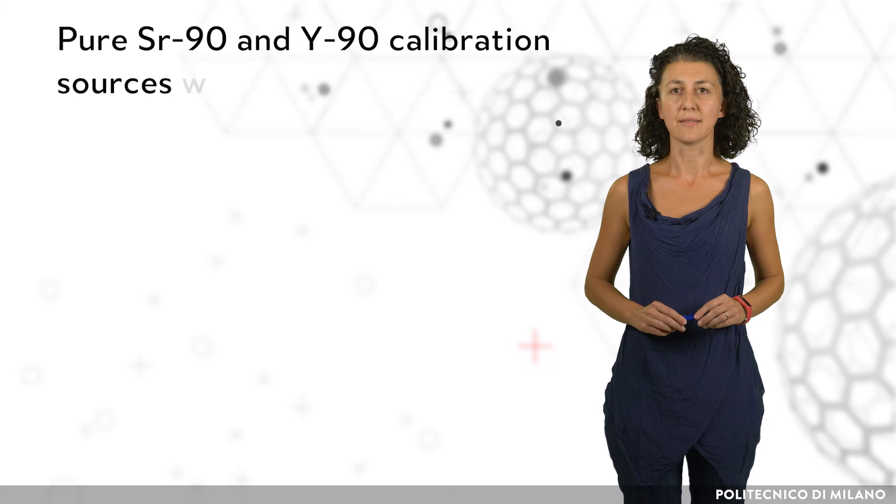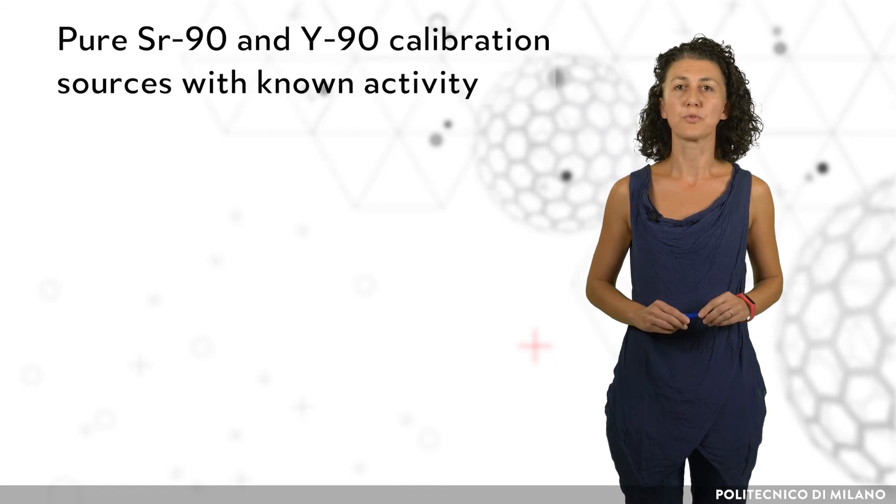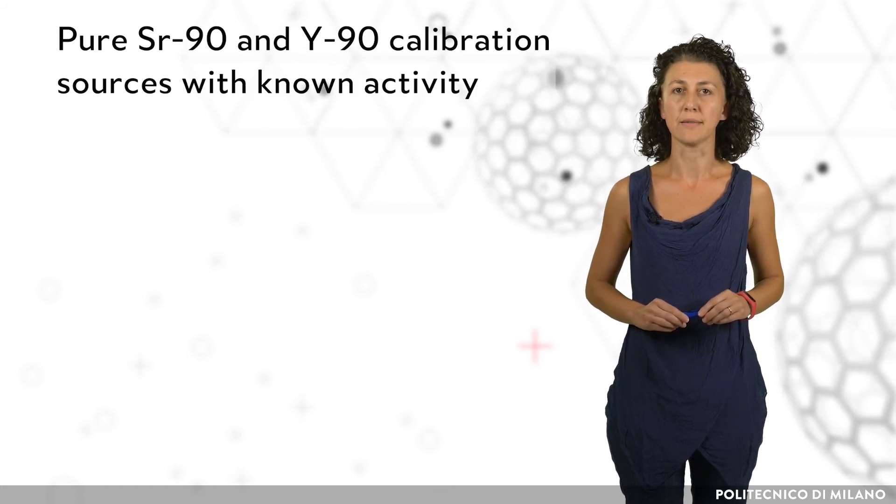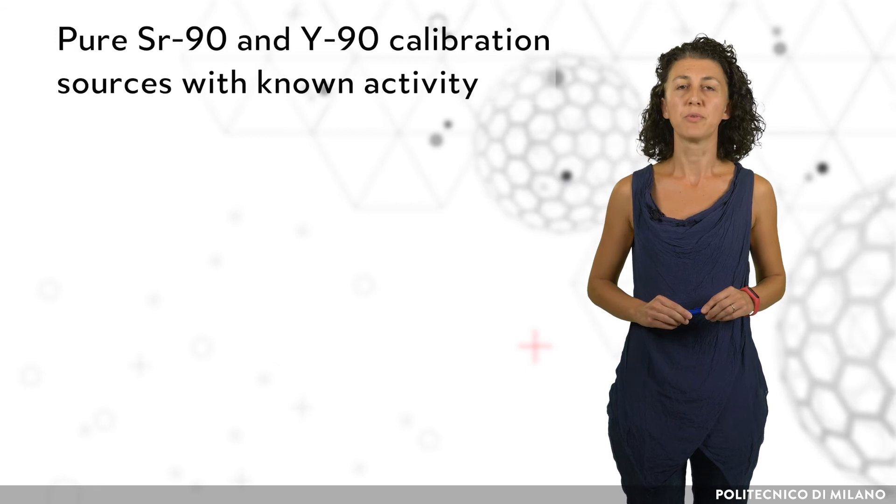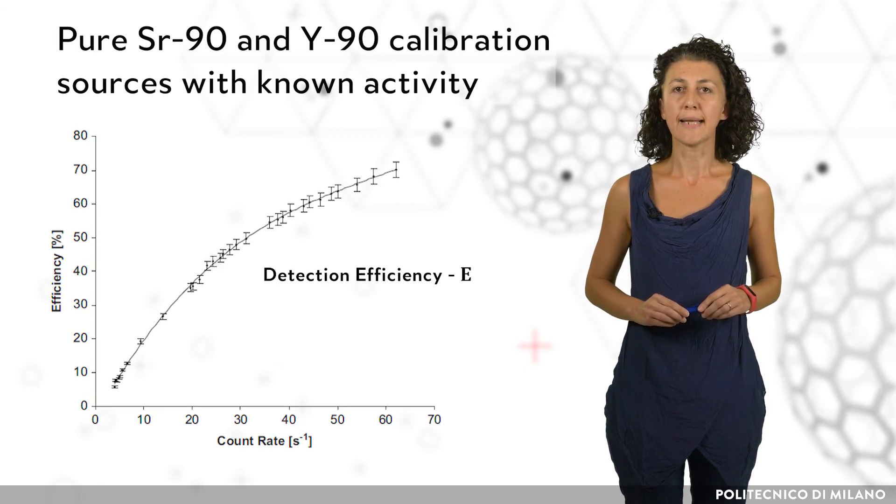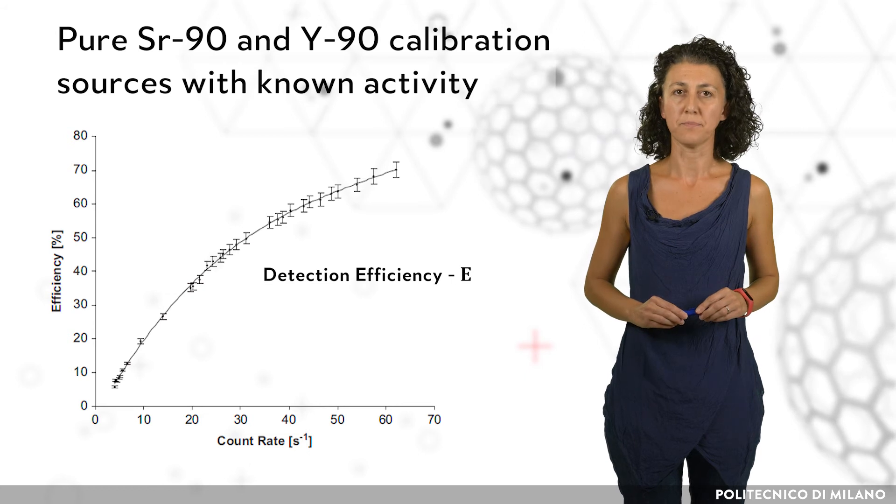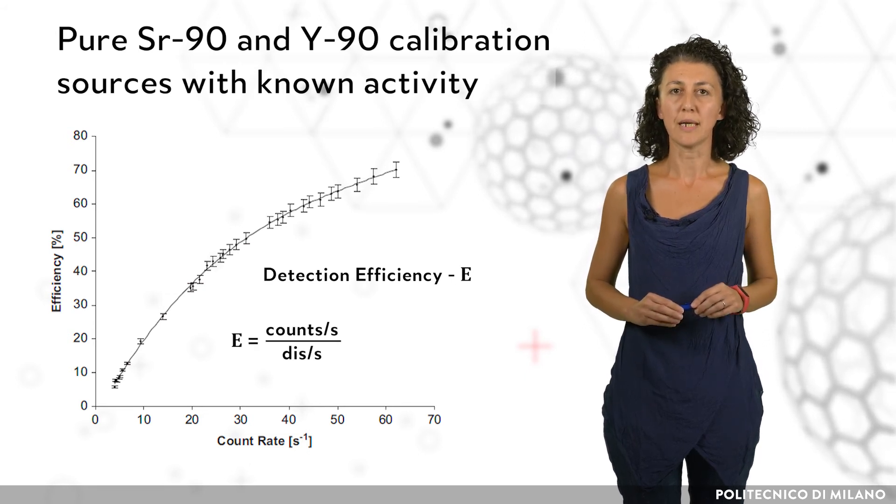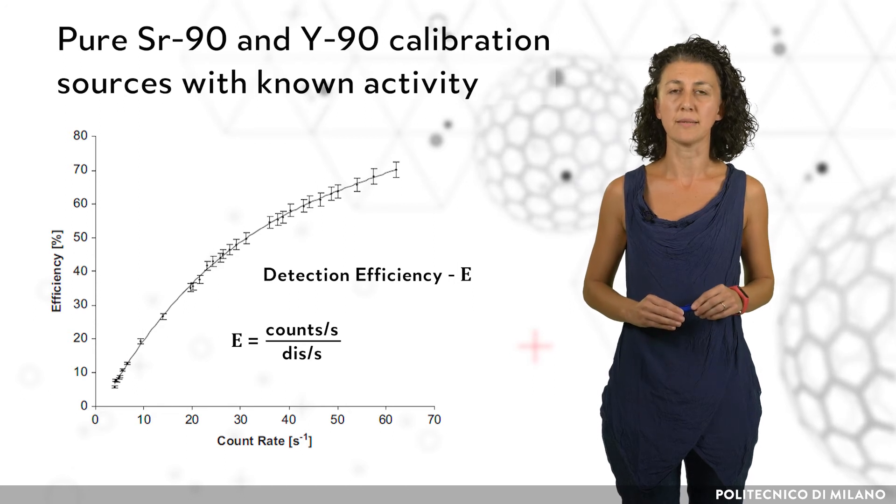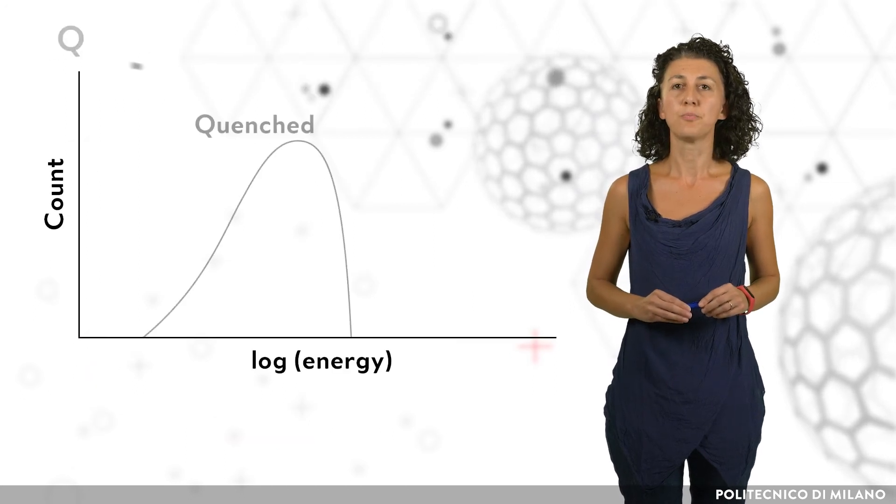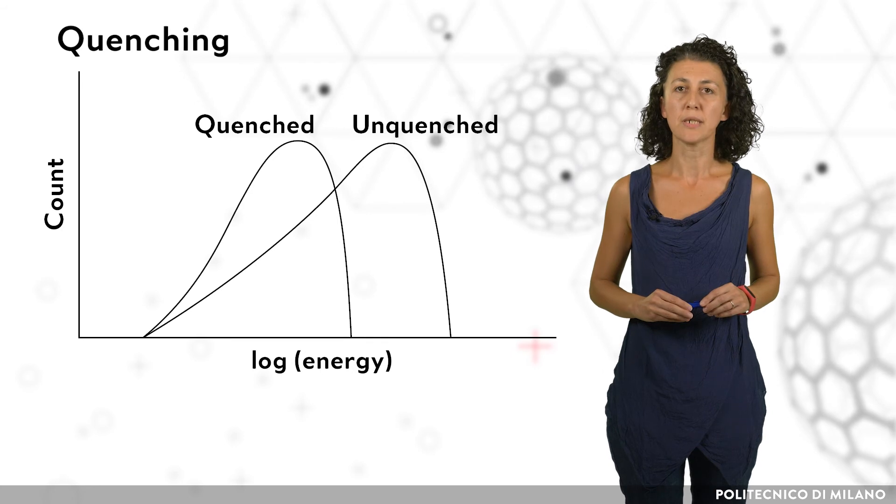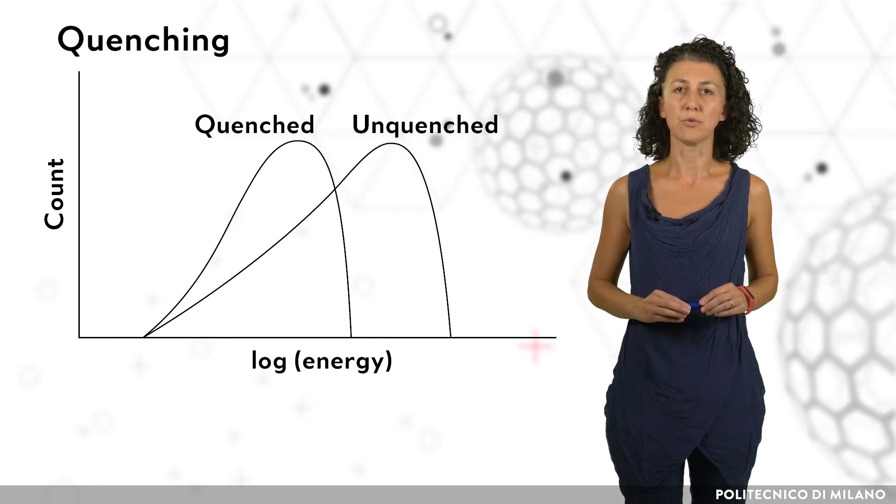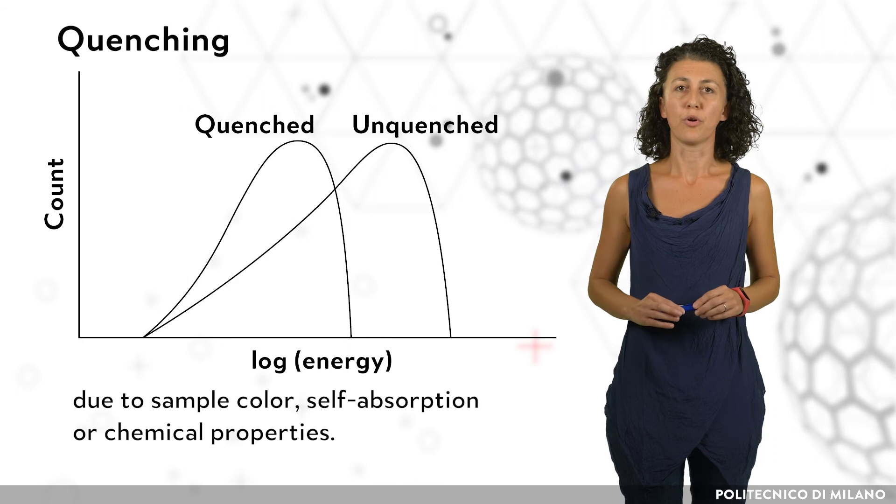It is necessary to prepare suitable pure strontium-90 and yttrium-90 calibration sources with known activity for determining the LSC detection efficiency. This parameter is defined as the ratio between the counts and decay events in the time unit. It could be influenced by quenching, a phenomenon that could give interfering counts due to sample color, self-absorption, or chemical properties.